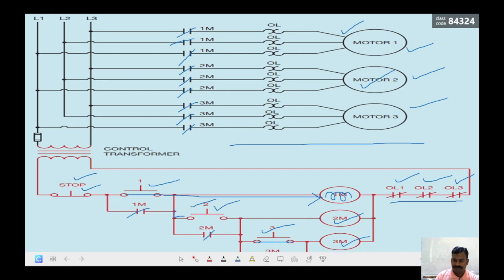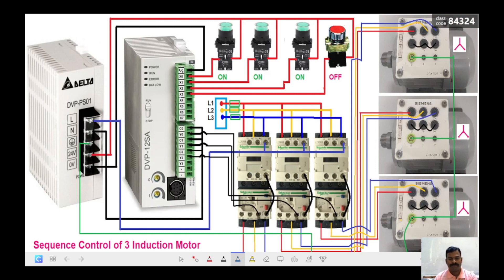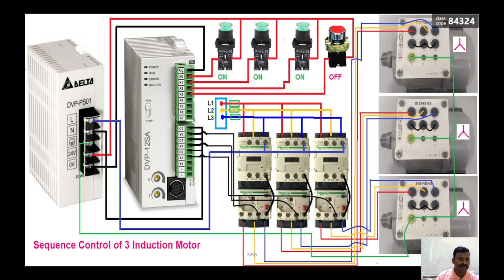This is the wiring diagram for the above control circuit and power circuit. We have the PLC here — this is the power unit, the PLC CPU — and the switching elements are connected to the PLC input card and the contactors are connected to the PLC output card. Since the PLC output card cannot directly drive the motors, we have the contactors here, and the contactor coils are driven by the PLC output card.